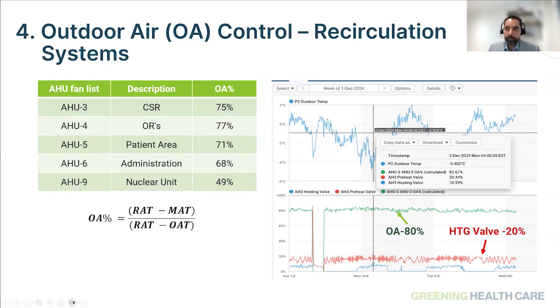And this was initially determined not through air testing, but just using the trends and the data from your building automation systems. You can ask your building operations team or controls contractor to set up this point on your graphics, so your operations team could see this outside air percentage and determine the next step, which generally is air testing, to ensure that you get the right amount of outside air. It also gives you a point where your operators are engaged on a daily basis, ensuring that you're bringing in the right amount of outside air and not over ventilating your facility.